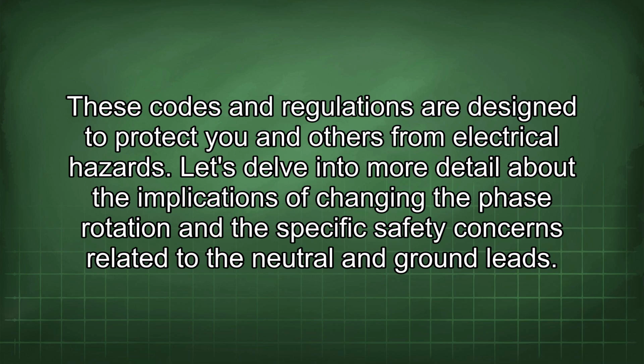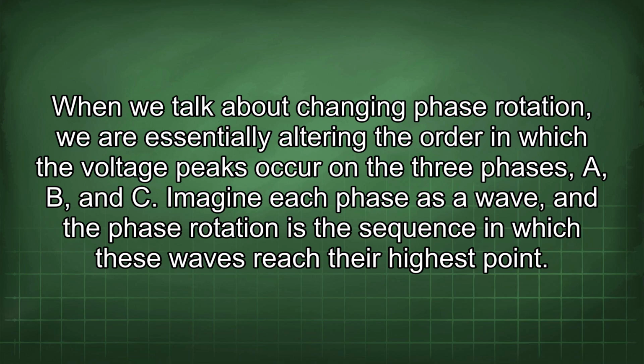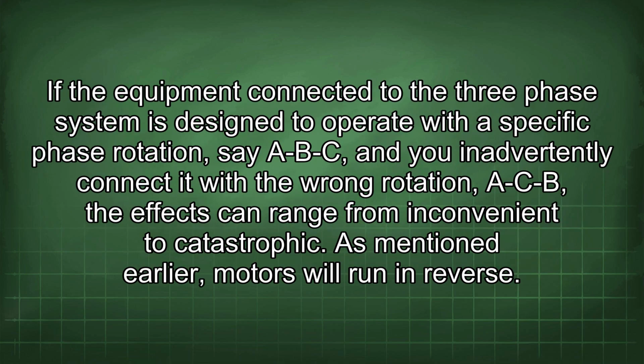Let's delve into more detail about the implications of changing the phase rotation and the specific safety concerns related to the neutral and ground leads. When we talk about changing phase rotation, we are essentially altering the order in which the voltage peaks occur on the three phases, A, B, and C. Imagine each phase as a wave, and the phase rotation is the sequence in which these waves reach their highest point. If the equipment connected to the three-phase system is designed to operate with a specific phase rotation, say ABC, and you inadvertently connect it with the wrong rotation, ACB, the effects can range from inconvenient to catastrophic.